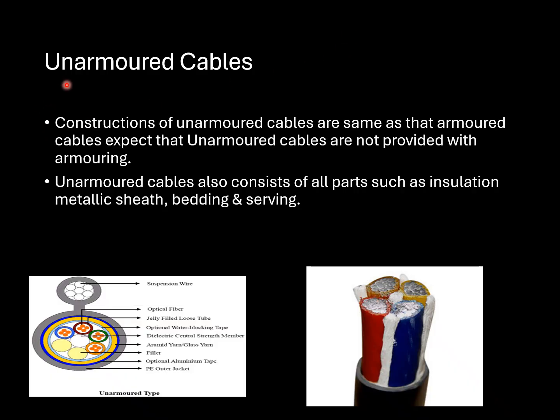Friends, unarmored cables are also used in higher ratings, but they go in such places where mechanical protection is not necessary, because they are cheaper than the armored category. The construction of unarmored cable is the same as that of armored, except that unarmored cables are not provided with armoring. Unarmored cable also consists of all parts such as insulation, metallic sheath, bedding, and serving.